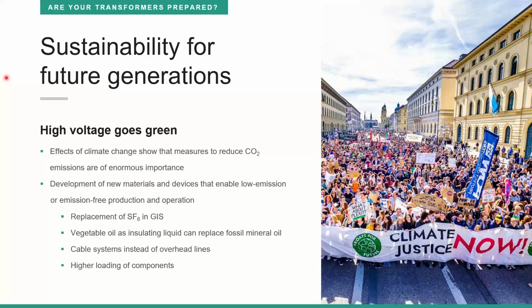So for high voltage, this means the development of new materials and devices that enable low-emission or emission-free production and operation. Some examples are the replacement of SF6 in gas-insulated switchgear, the use of vegetable oil as an insulating liquid, which can replace fossil mineral oil, the use of cable systems instead of overhead lines, and of course also higher loading of components.